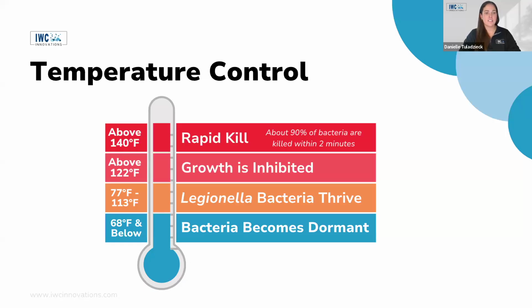Temperature control. Legionella bacteria grow across a wide range of temperatures, but they thrive best in warm waters between 77 and 113 degrees Fahrenheit. Growth slows outside of this range, but it doesn't stop entirely until the temperatures are much lower or much higher. Below 68, bacteria become dormant but still survive. And then above 122, we start to see inhibition of the growth. When we reach 140, about 90% of bacteria are killed within 2 minutes of contact time. As we approach hotter temperatures, just above 150, we get rapid kill where the bacteria die in seconds. Above 160, Legionella is eradicated almost instantly.